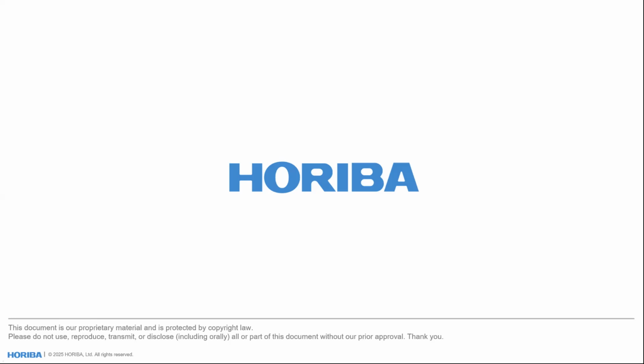Right, and we'll end on, does Horiba offer technology to reduce laser power at a sample or distribute power during measurements to avoid thermo or photo-induced damages? Yes, we do have two different technology that can be integrated in our system, which allows you to raster the beam, and this really drastically reduces power density at the sample. Yes. All right.